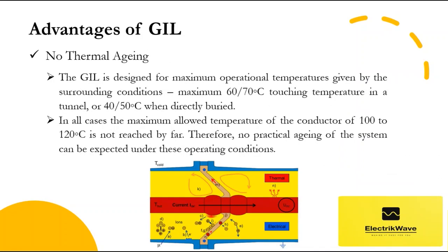GIL has no thermal aging. The GIL is designed for maximum operational temperatures given by the surrounding conditions — maximum 60 or 70 degrees Celsius touching temperature in a tunnel, or 40 or 50 degrees Celsius when directly buried. The different temperature values depend on individual countries and their applied standards and regulations. In all cases the maximum allowed temperature of the conductor — 100 to 120 degrees Celsius — is not reached by far. Therefore, no practical aging of the system can be expected under these operating conditions.